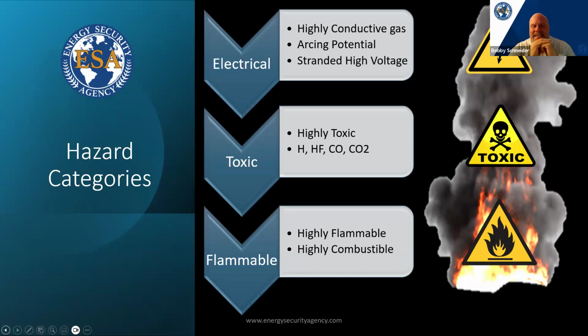What we've seen is that we're looking at 1 to 5 liters of off-gassing per watt hour, or a comparison of about 2 to 10 liters per amp hour. So there's a massive amount of off-gassing when this happens, and that range is because of the different chemistries. So when I'm putting off that much hydrogen and CO, I'm creating something explosive and flammable.